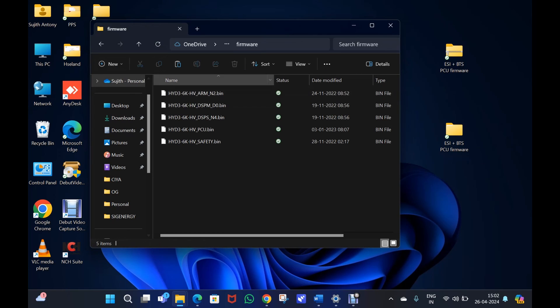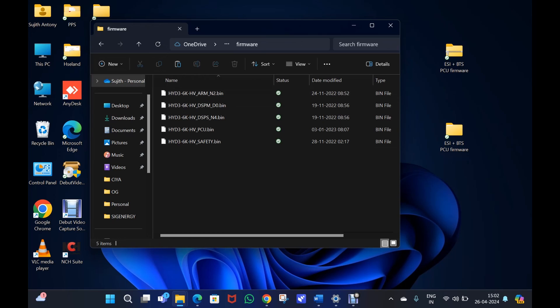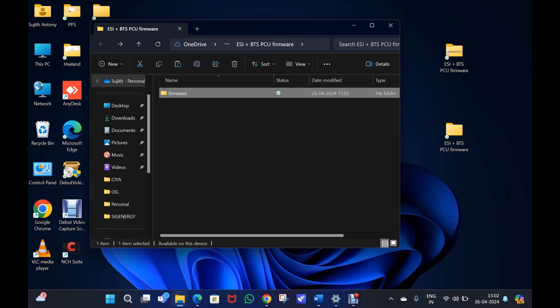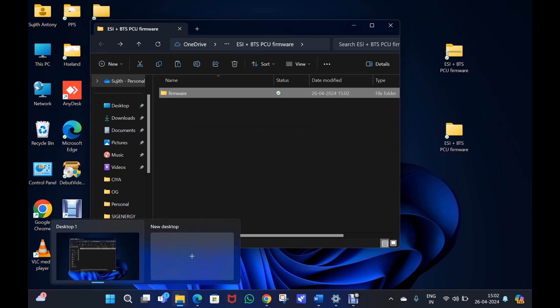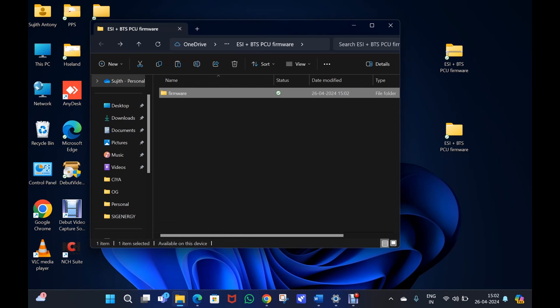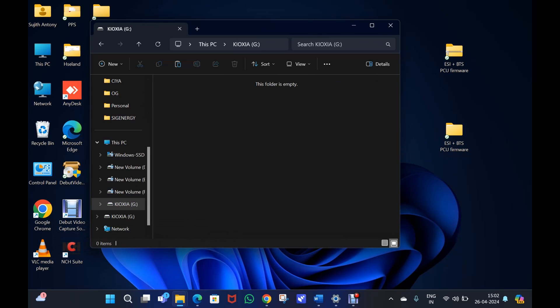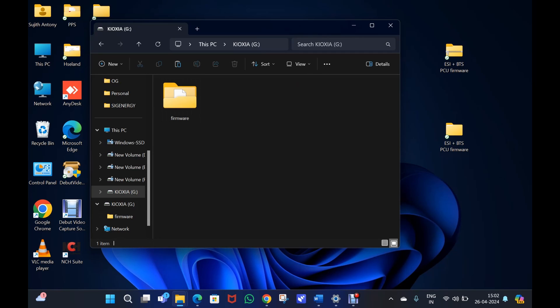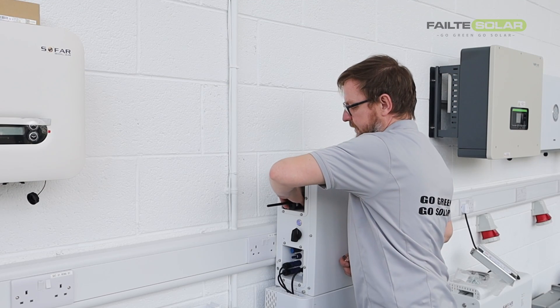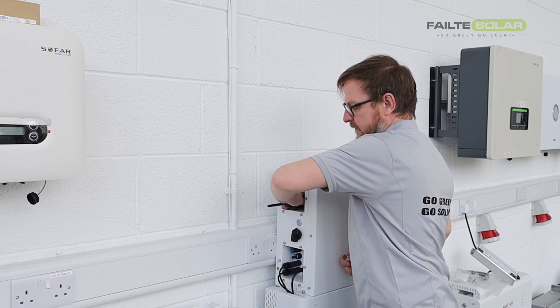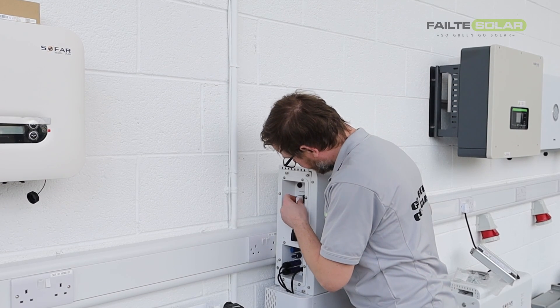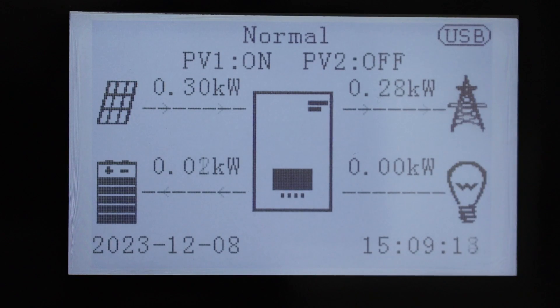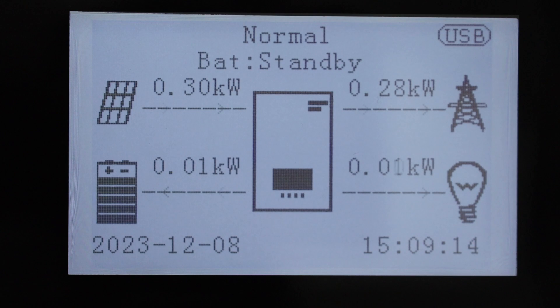Inside the folder you can see bin files. We need to copy the firmware folder and place it onto the USB that was previously formatted. With that we can approach the inverter and start the upgrade. First thing will be to remove the current logger, put in your USB. The USB symbol should be visible straight away.